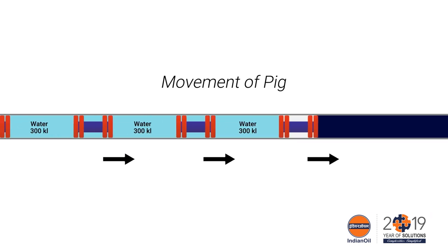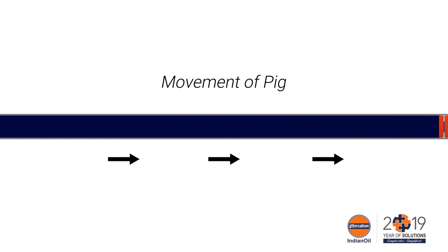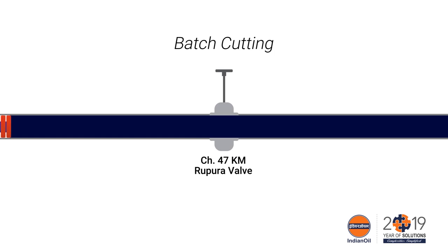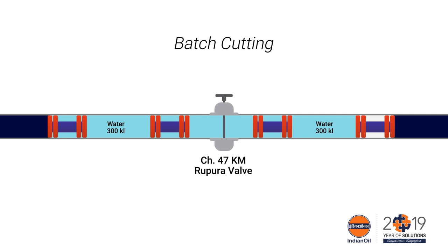Here the pig train is moving through the pipeline. The train of pigs separated with water parcels was tracked and batch cutting was carried out at Rupura valve. Only two pigs were allowed to cross this valve and then the pipeline was made shut down.